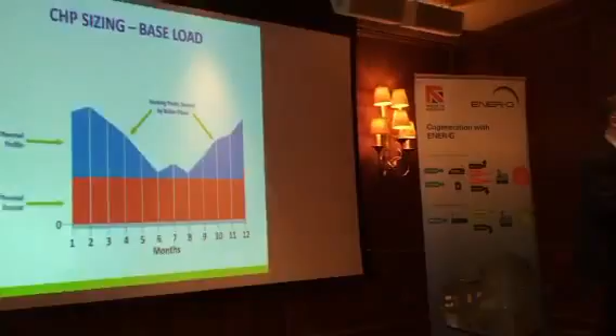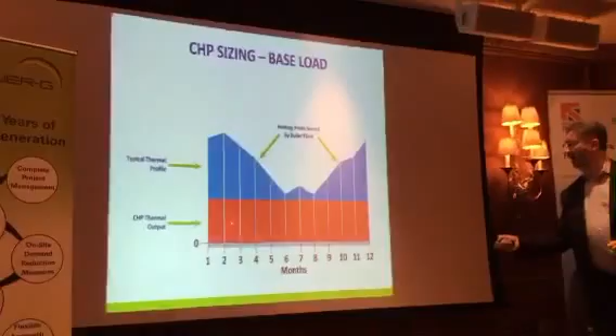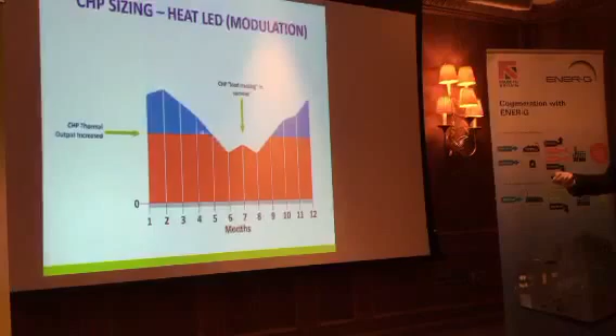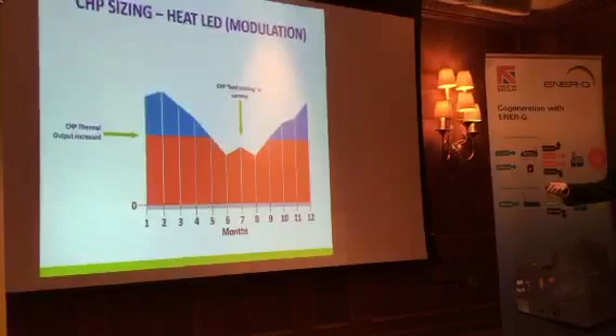Now, let's go back to that sizing. You take a very conservative approach. Here's my thermal load, and the CHP here is just doing the base load. The myth goes around that you just size CHP on the base load, but I think that's far too conservative. You're not getting as much out of it as you would if you went for a slightly bigger CHP, though in summer the load is lower, and what we're doing is modulating the machine.